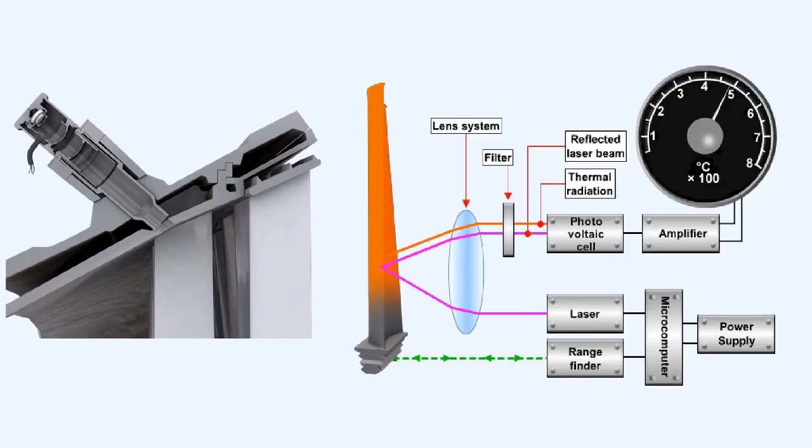A radiation pyrometer is a device which can convert radiated energy into electrical energy. It consists of a photovoltaic cell and a lens which focuses the radiated energy onto the cell. The pyrometer is positioned so that the lens can be focused directly onto the heat source, in this case, the turbine blades. The photovoltaic cell converts the radiated energy emitted by the blades into electrical energy, which is passed through an amplifier to an instrument calibrated in degrees Celsius.